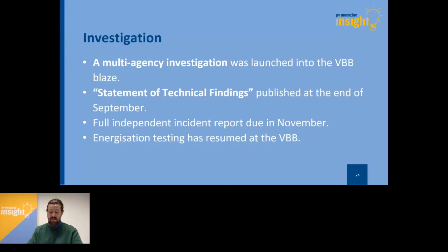With the assistance of testing undertaken by Tesla, an examination of the scene by ESV, and video surveillance and telemetry data, ESV concluded that the most likely root cause was a leak within the first megapack's battery pack cooling system, which caused a short circuit and a fire in an electronic component. This resulted in heating, leading to a thermal runaway event and fire in an adjacent battery compartment within the first megapack, which then spread to an adjacent megapack.